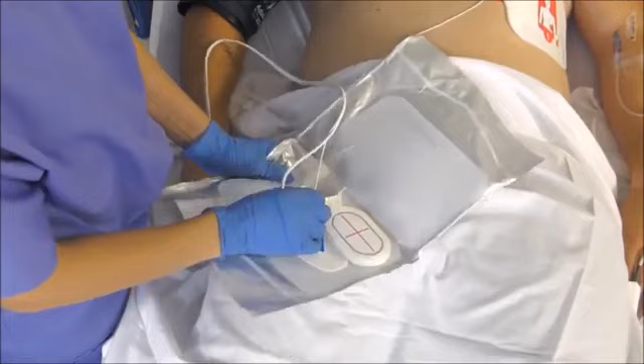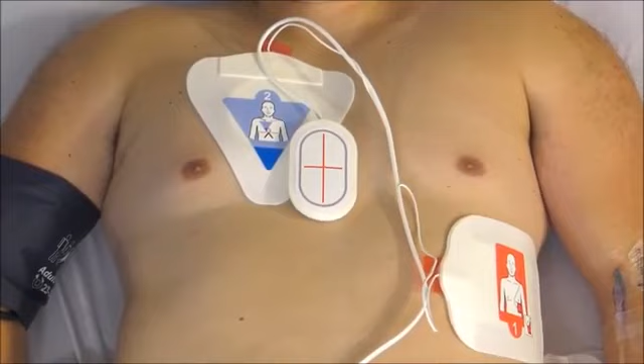Align the CPR sensor on the patient's chest so the vertical red line is mid-sternum and the horizontal red line is between the patient's nipples. Roll the electrode onto the patient's left chest with the blue triangle midway between the sternum and nipple. Apply on the patient's upper right torso. Placement of the apex electrode varies slightly in the anterior-anterior configuration. The more lateral placement increases the likelihood that more of the heart musculature will be within the current pathway. One-step CPR anterior-anterior electrodes can be positioned in an anterior-posterior position if needed.